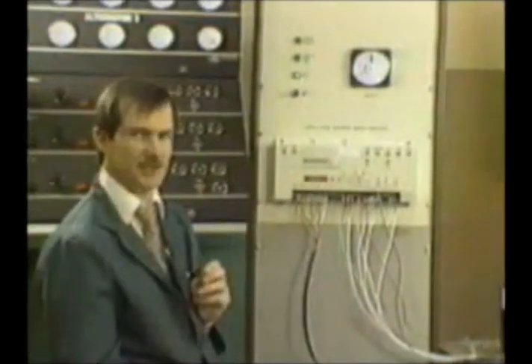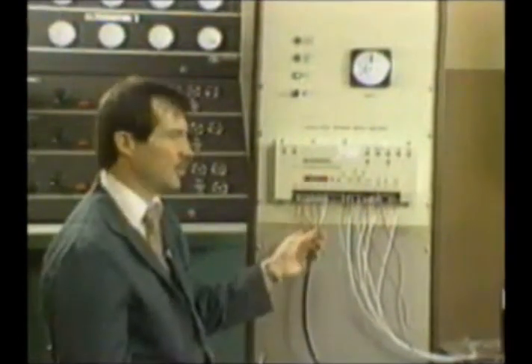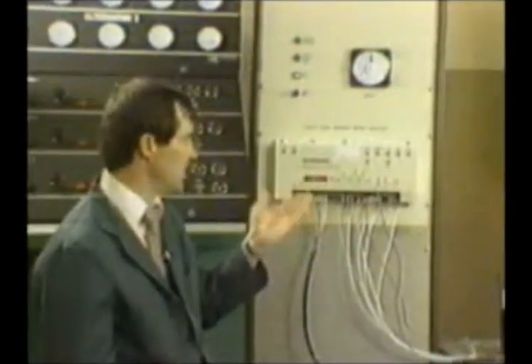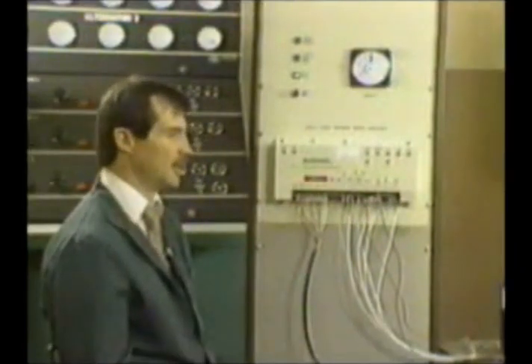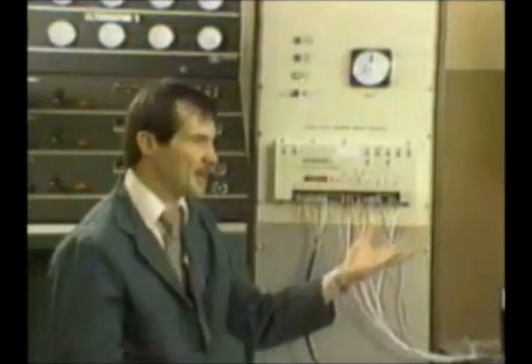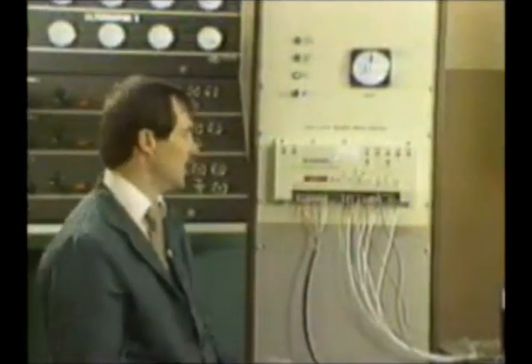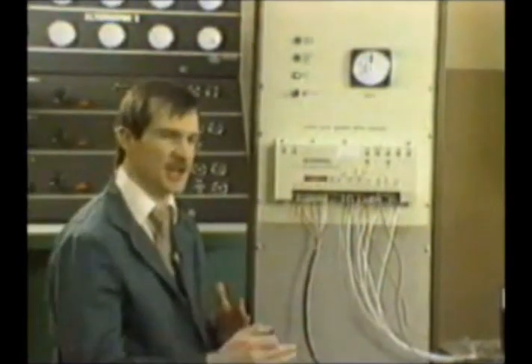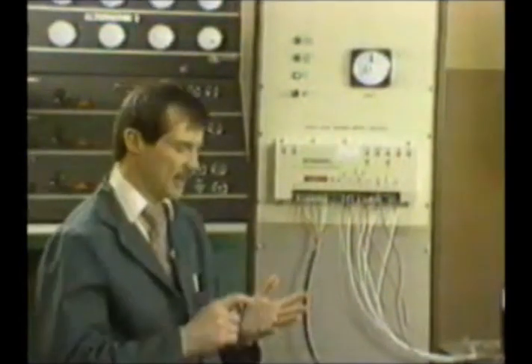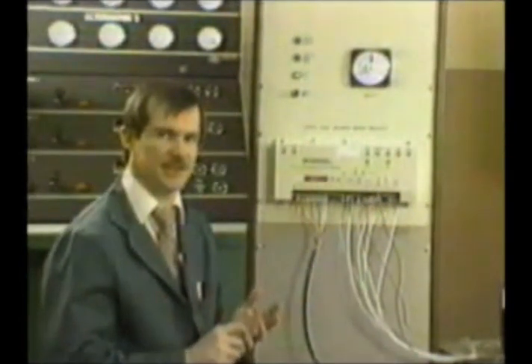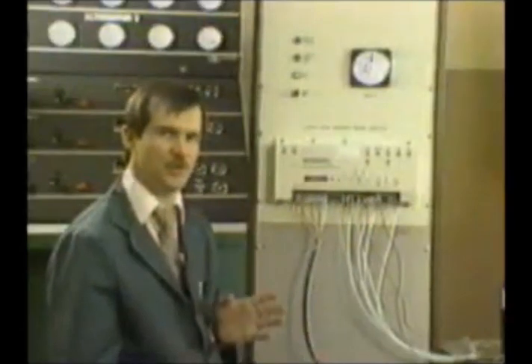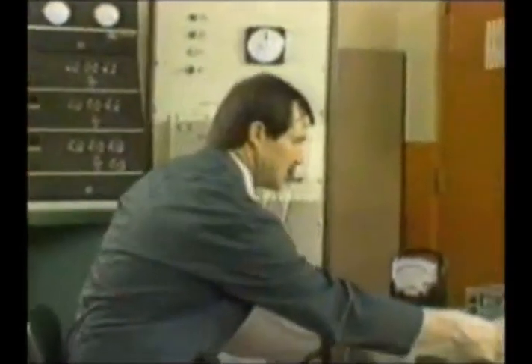To set up your load gain voltage, you need to have load on your engine so that the CTs are giving us a signal. Now, in your situation, you might not be able to have a resistive load bank to load up the unit fully. So if you can get a percentage of what you know is the maximum load of the engine, then you want to set up your load gain signal for a percentage of what you would set your load gain voltage at for your maximum load. So at 100% load, if you want a load gain voltage of 6 volts, and you only have on a third of that load, you want to set up your load gain voltage for 2 volts at that point. So let me point that out here.